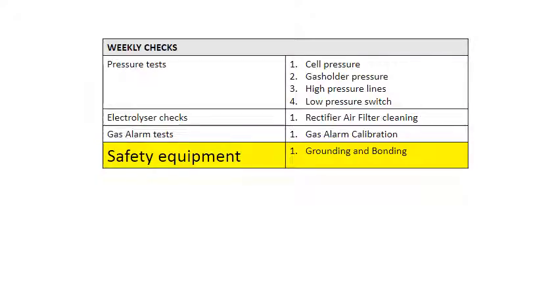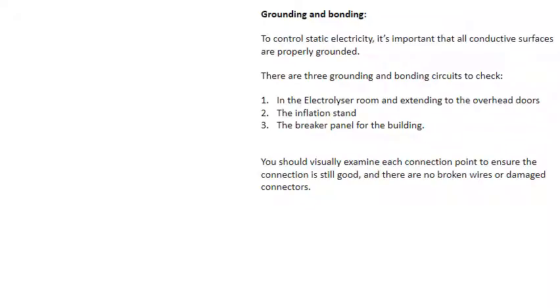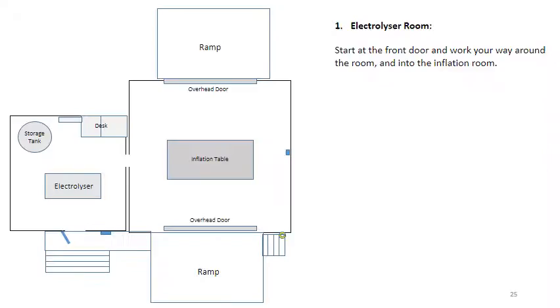The safety equipment check is primarily grounding and bonding. To control static electricity, it's important that all conductive surfaces be properly grounded. There are 3 grounding and bonding circuits to check: in the electrolyzer room and extending to the overhead doors, the inflation stand, and the breaker panel for the building power as a whole. You should visually examine each connection point to ensure the connection is still good and there are no broken wires or damaged connectors.